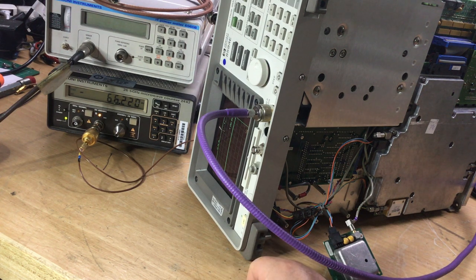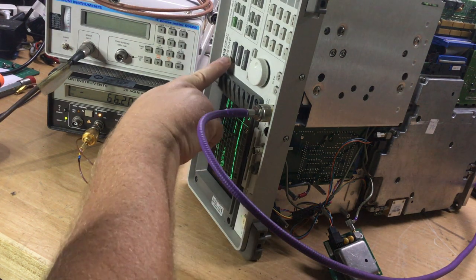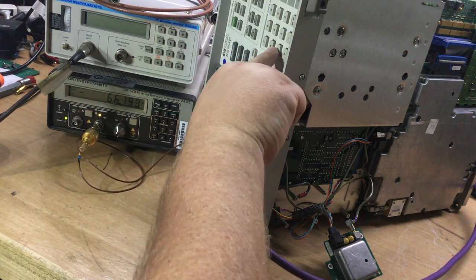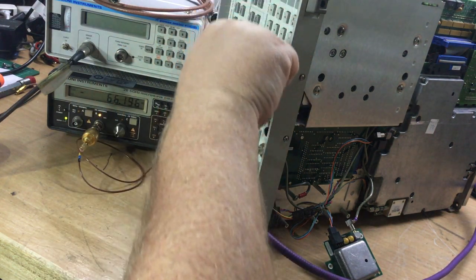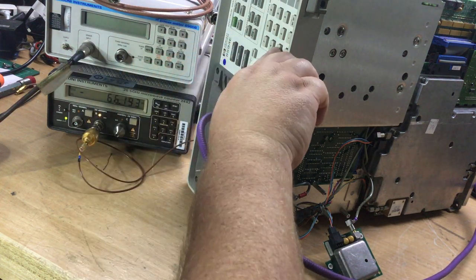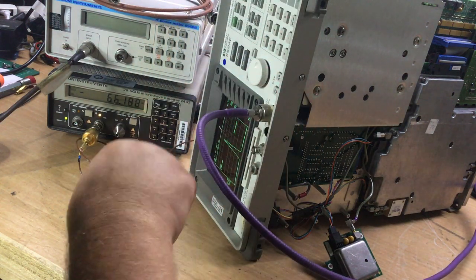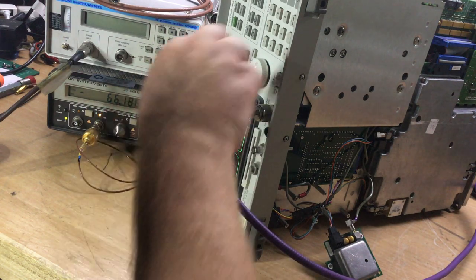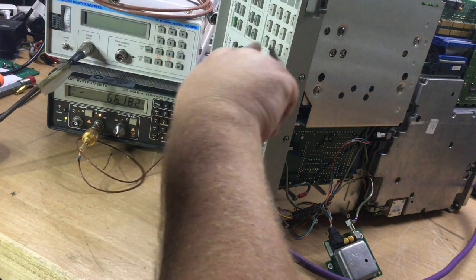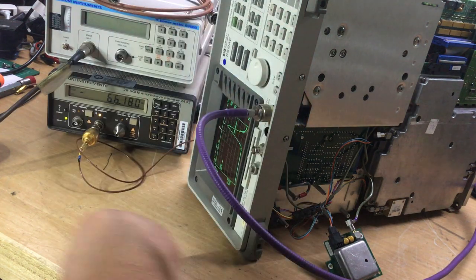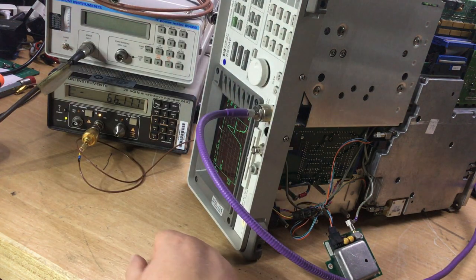It would have just vanished, because without a reference oscillator running, there would have been nothing to compare the signal with, and therefore it wouldn't have been able to display the signal in the first place. So let's set the frequency then to 100 megahertz, a span of 1 megahertz, and we'll have the amplitude. Yeah, that's okay. I'll set the span again just to see whether we can still get 50 kilohertz, and we can. So it's not as if it's made any major change.